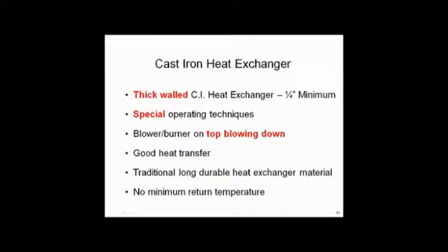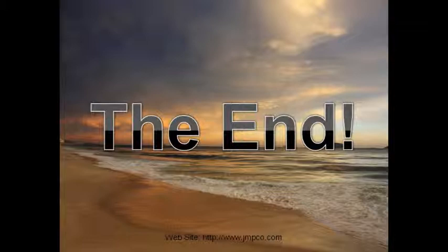They do some special operating techniques to try to blow the condensate off the top of the heat exchangers a little bit, and they give you good heat transfer. There's no minimum return water temperature. They're fairly durable heat exchangers, as long as you can accept the fact that they're going to rust on you, and you're going to be eating into them over a period of time. So that would be the only comments there. They do work as long as you accept the fact they have to be thick. You've got to make sure you've got thick cast iron.